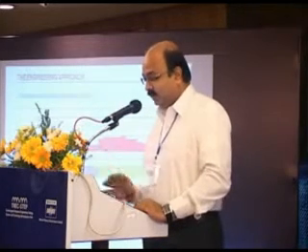So if the information is available as to how many hours were spent in what condition, the survey will help us make the right decision. And then you can make time histories and see the temperature behavior, what happened. And you see here how many hours at what temperature, a bell curve kind of a thing shown there. And in the first case, it's much below the design, so you're fine. You don't have to worry about those areas.